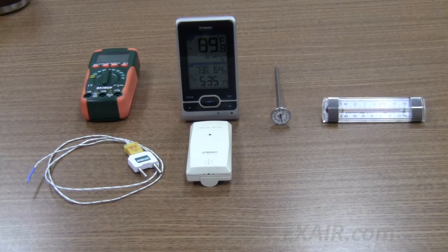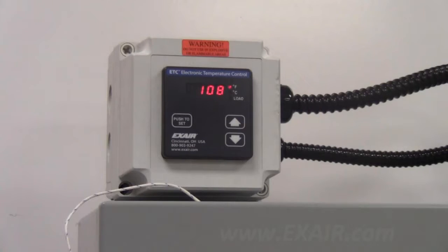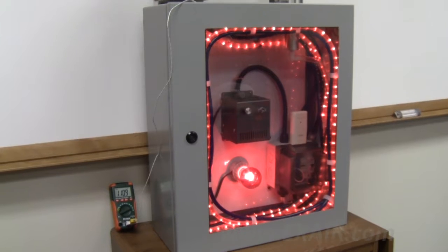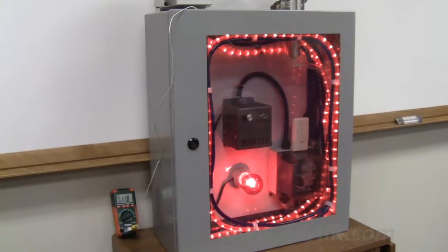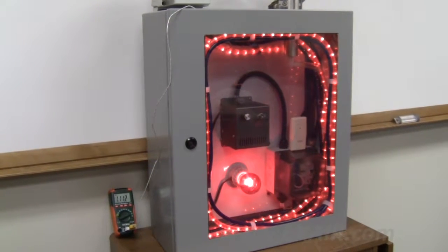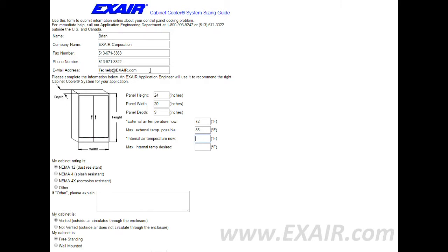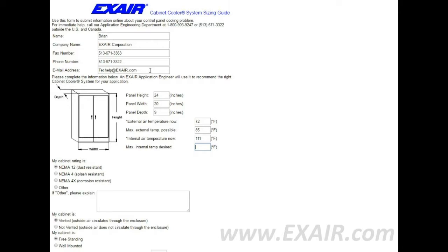Measure the internal air temperature now using one of many possible temperature measuring devices. Here we're using a thermocouple and meter. Next, record the maximum internal temperature desired. Typically 95 degrees Fahrenheit is a good temperature for today's electronics.